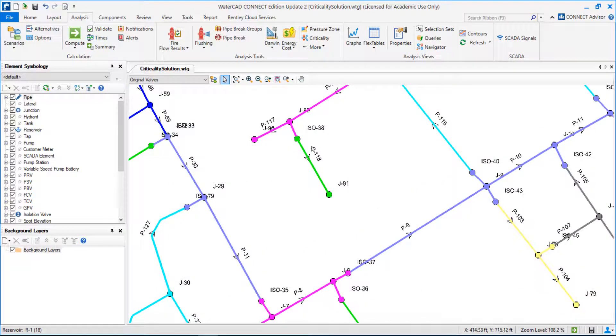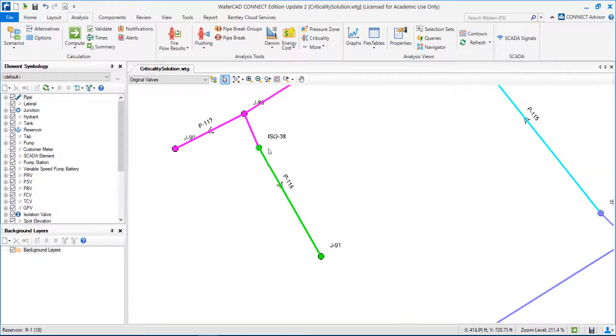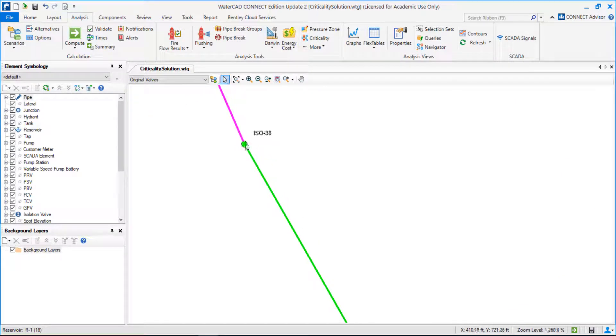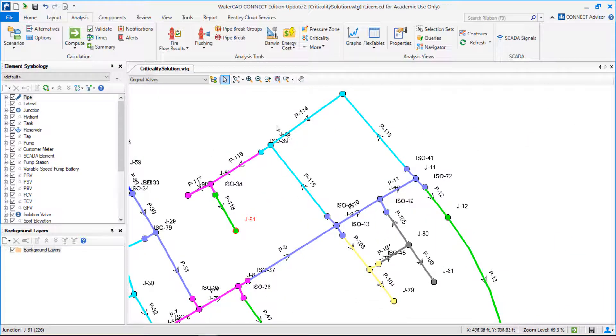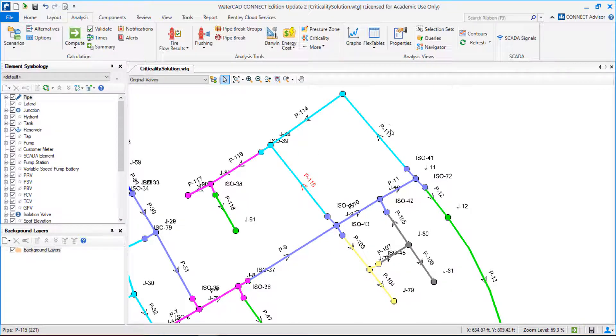For example, if I zoom to this pipe, this represents a segment because I have one valve here, and if I close this valve, I will isolate this pipe. If we go to the middle, for example, we have this segment with light blue. This segment is composed by these pipes: 115, 114, 113.